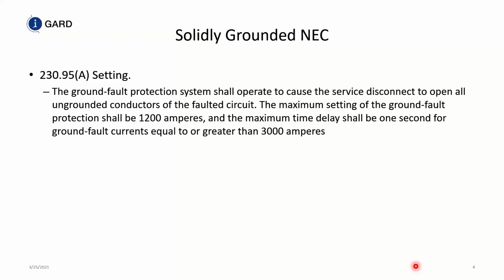So 230.95(A) says the ground fault protection system shall operate to cause a service disconnect to open all ungrounded conductors of a faulted circuit. This is predominantly a ground faulted circuit because the maximum setting of the ground fault protection shall be 1200 ampere. The reason that we have to disconnect an electrical circuit when there's a ground fault, and specifically have LSIG functionality on a disconnect, is because ground faults can often go undetected and can cause fires if they're not eliminated quickly. So as you can see here, the maximum time delay shall be 1 second for a ground fault current equal to or greater than 3,000 ampere.